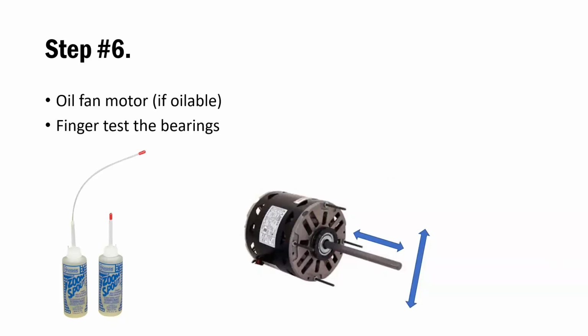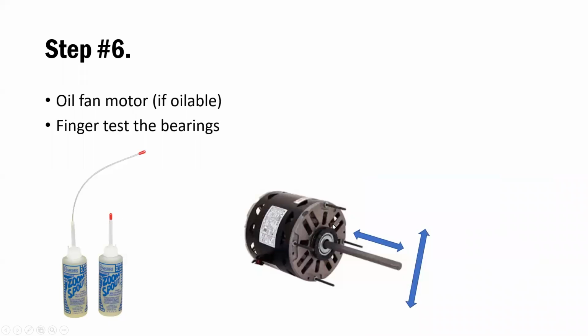Next, we oil the fan motor if it's oilable, and we're going to do the finger test on the bearings. So you're going to have a fan motor here, as you can see on this picture. On this picture, they just removed the fan motor so they could clean it, which is what we do. So the finger test is just this shaft right here that spins the fan blade, that moves the air through that coil. It's okay for it to have play in and out, but it should have no play whatsoever up and down. Like if it's laying on its side, it would be up and down. So we always test that, because if you have any play whatsoever, it means that the bearings are starting to go bad in that motor.